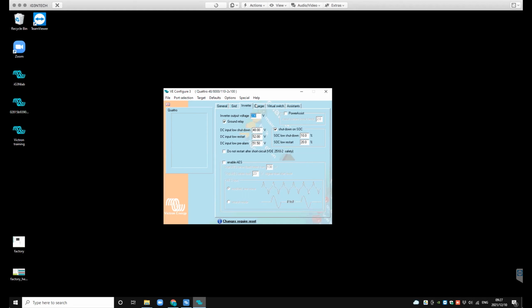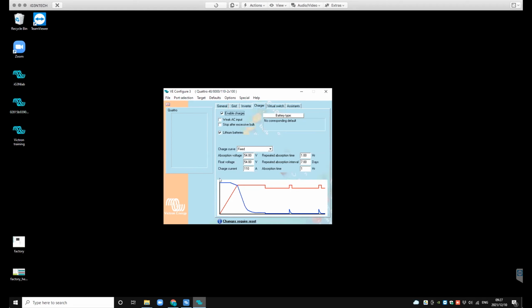The next tab that we're going to look at is the charger tab. This is also just a fallback should the CAN bus fail, because the CAN bus essentially tells the system at what rate it needs to be charged and discharged. So these are all fallbacks. Make sure that lithium battery is selected. And then on the iGen products, we basically have one set point for absorption and float, and that is 54.